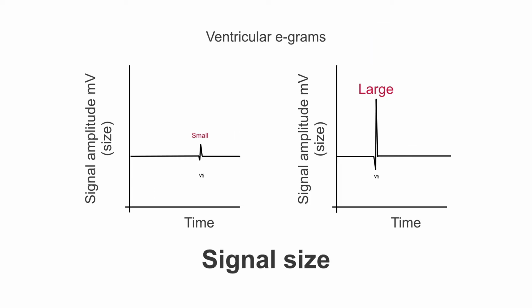sensed event. Now, you can get different size deflections on your E-grams, so different amplitudes in millivolts. This can be down to the amount of tissue depolarizing, the position of the lead, the contact of the lead with the myocardium, and even the direction of the current. I think of this as how loud the signal is. You can have a small signal, which is quite quiet, or a nice large signal. When we implant a pacemaker, we want to ensure we have a nice loud signal because that makes life easier in the long run, and now we'll see why.